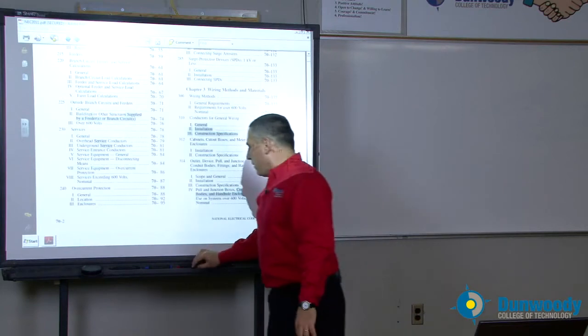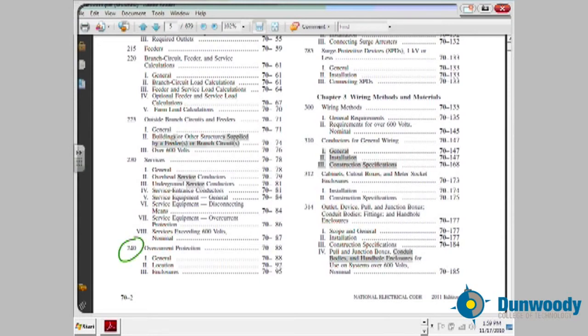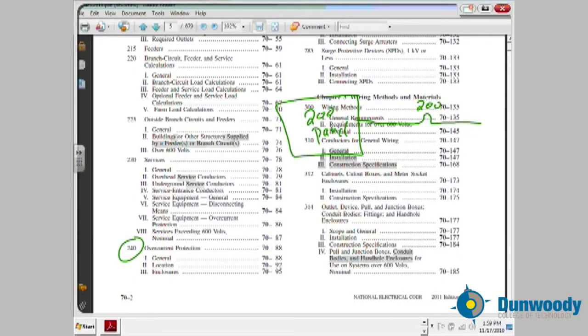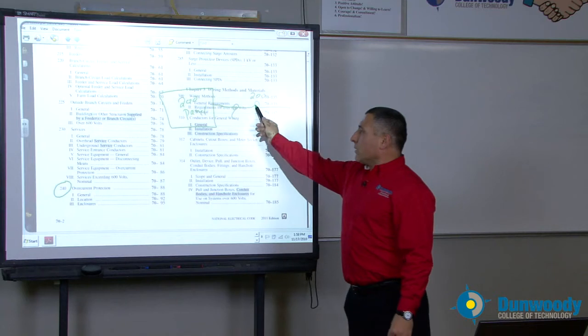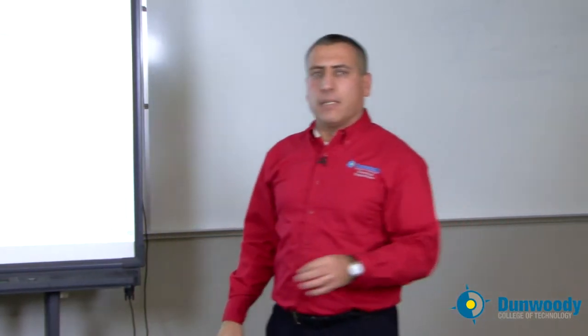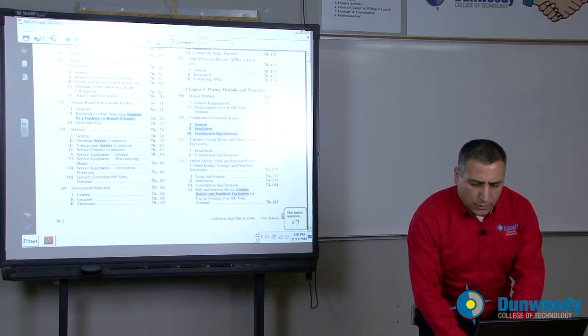Another very important topic is overcurrent protection devices. Every time we have a conductor that needs to carry a load, you need an overcurrent protection device. For example, a 200-amp panel must be protected by a 200-amp circuit breaker and wired through conductors — whether a feeder or service. The conductors and the panel must have an overcurrent protection device sized correctly to protect both the panel and the conductors.